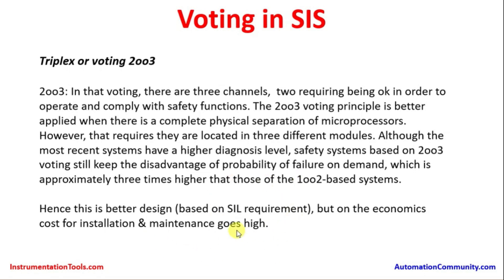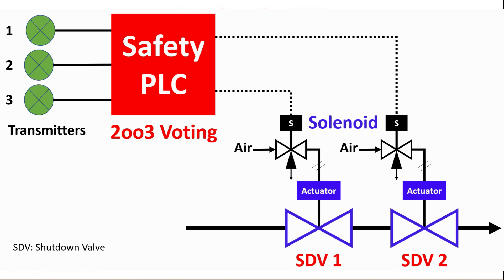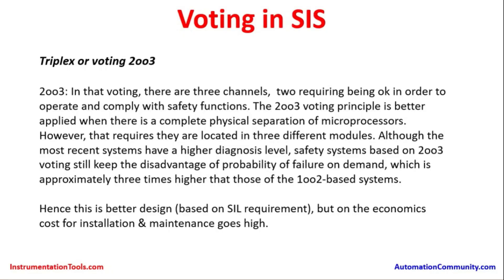In overall composition, 2 out of 3 is a better design from a safety perspective, but on the economics side — considering cost of installation, maintenance, proof testing of all 3 transmitters, and valve seat leakage checks — the maintenance cost will also be high. However, if the SIL calculations require a 2 out of 3 arrangement, it is the ideal choice for safety, even though it is a disadvantage economically.